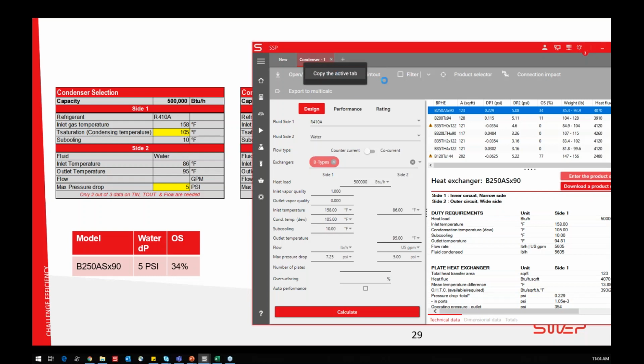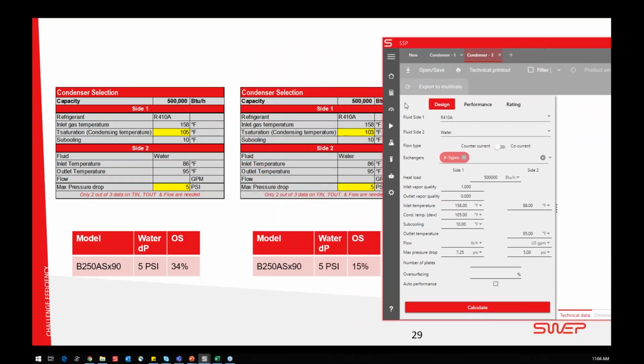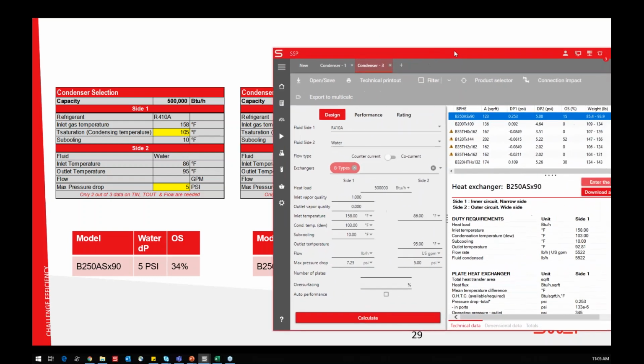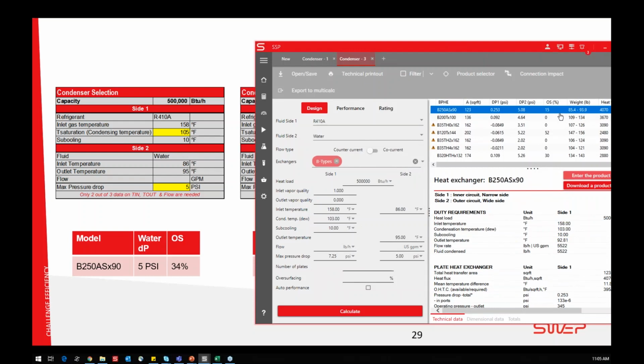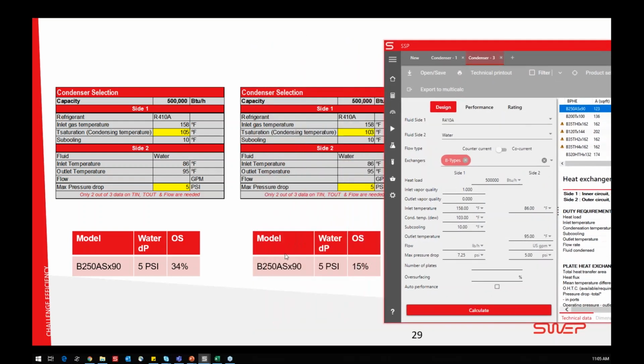Okay, so we do the calculation of the second case. What do we change there? We went down 2 Fahrenheit in the condensing temperature, but everything else is the same. Let's see what happens. It's already here, right? But I want to make you see it. It's exactly the same heat exchanger. The pressure drop is the same. Over surface is still there, but it went down. Here we had 34% over surface because it's related to the 105. Now it's 15% because it's related to 103, but it's still a little bit over dimension. It's not a problem, either one of these, but it means that the limit of the pressure drop and the target performance cannot be met, so we have to over dimension the heat exchanger a little bit.